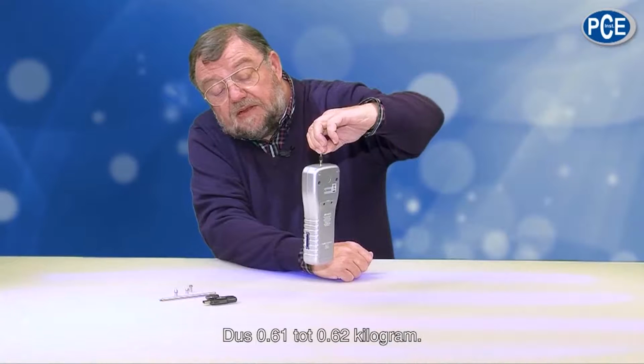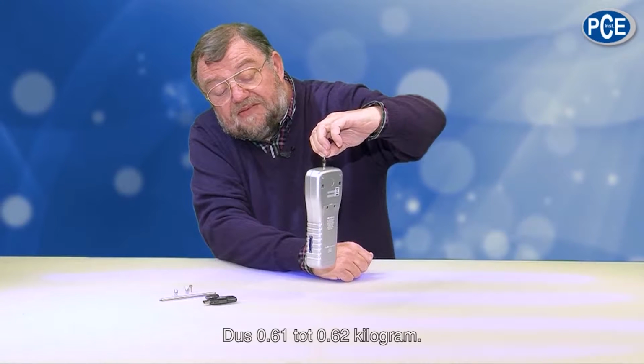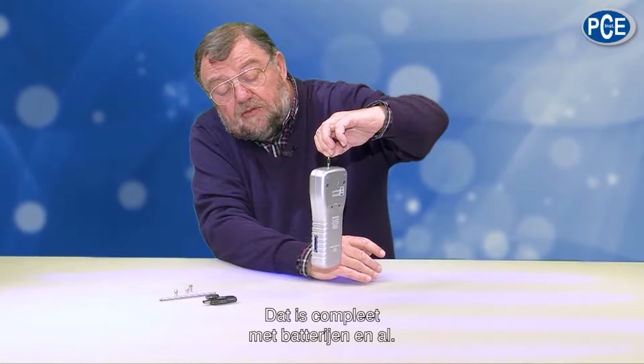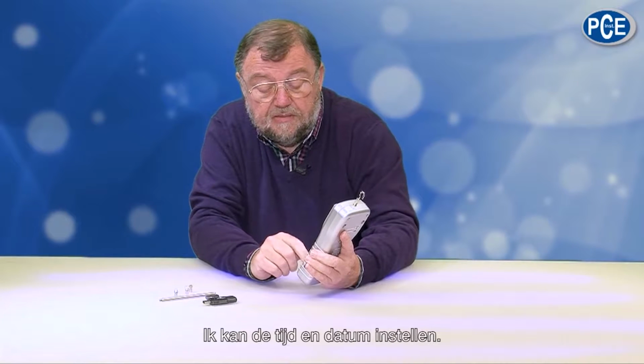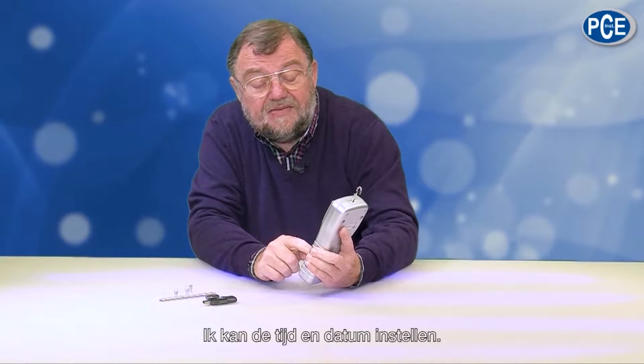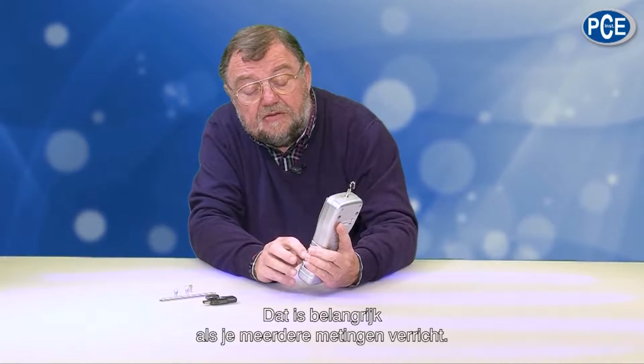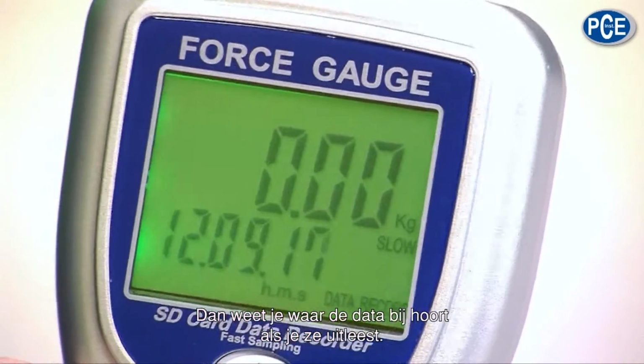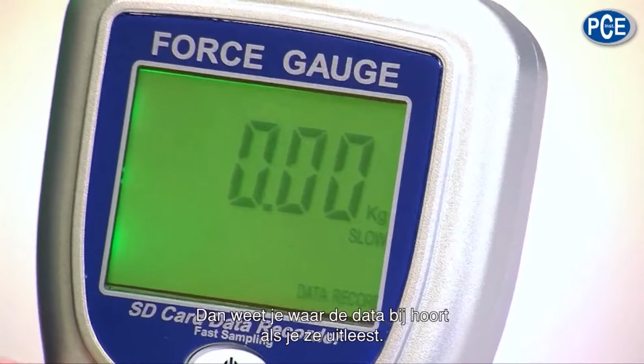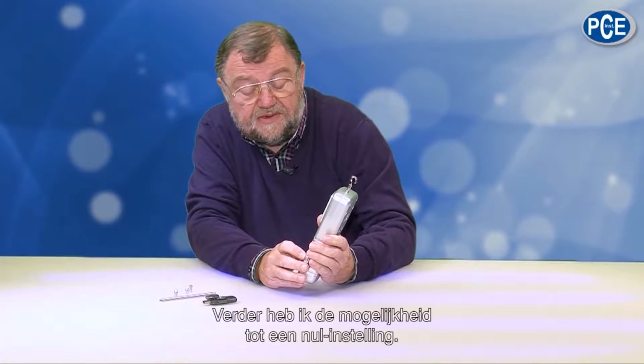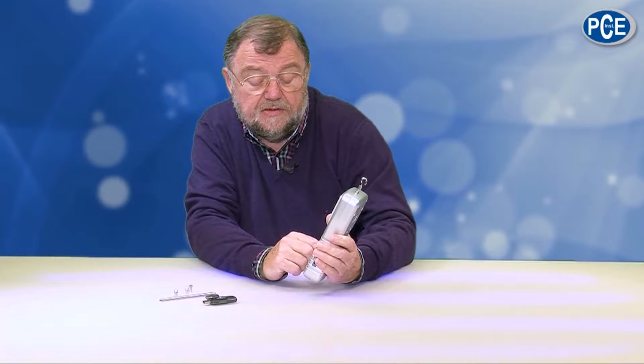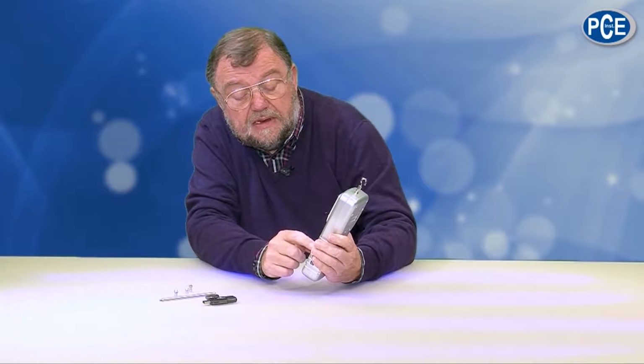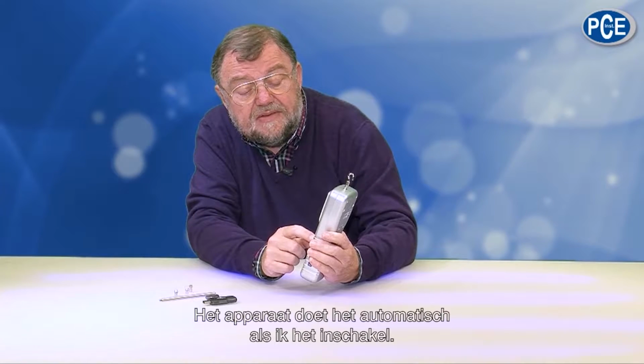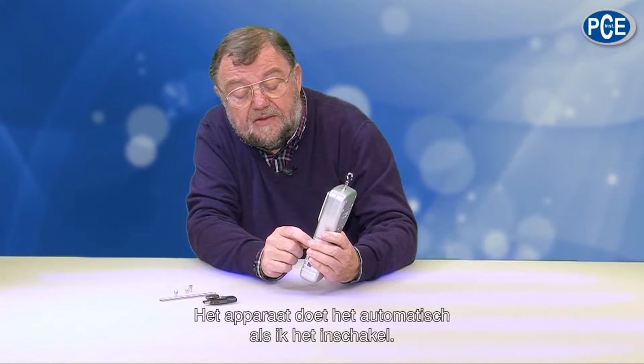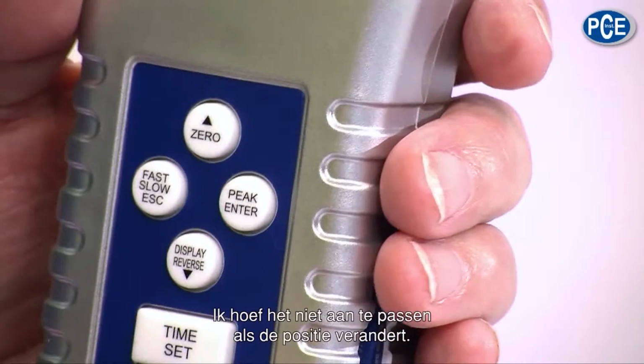So 0.61 to 0.62 kilogram, complete with batteries. And then you can go into different menus. I can set the time and date. That is important when you are doing measuring rows, so you know what the data recordings belong to when you read them. And then I have the possibility of the null setting. The device does that automatically when I turn it on. I only have to change it when the position is changed.